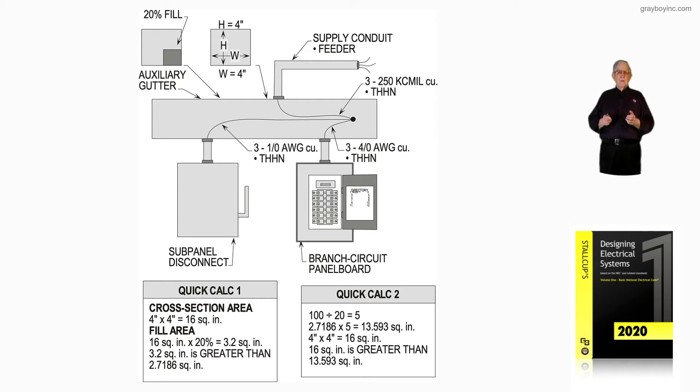Quick calc 1: if we used a 4x4 auxiliary gutter, and I will call this out again, the back inside cover of each design book, volume 1 and 2, has the standard size auxiliary gutters that you could purchase. A 4x4 is 16. You're allowed 20% fill in that auxiliary gutter. So 20% of 16 is 3.2 square inch area. 3.2 square inch area is greater than 2.7186 when we do the calculation.